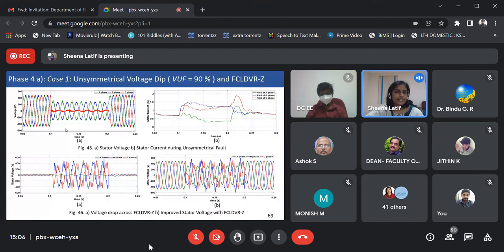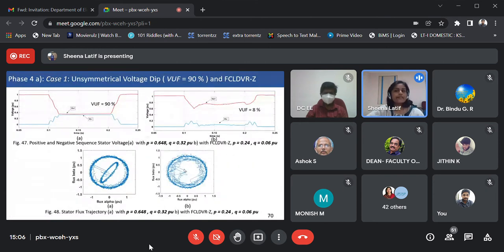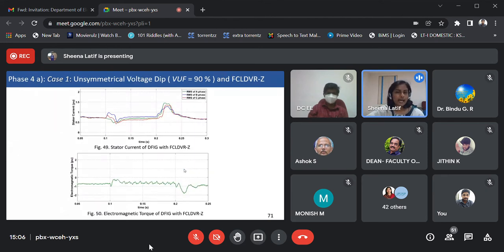As a result of the FCL DVR impedance activation in the B and C phases, the voltages across these two phases are improved, and the improved stator voltage is shown in figure 46B. As a result of the FCL DVR impedance action, the VUF is now reduced to 8% from 90%, which is a very good result. And also the stator flux trajectory, which was following an elliptical path, is now restored to the circular trajectory. The stator current after FCL DVR impedance action and the electromagnetic torque regulated after FCL DVR impedance are shown.